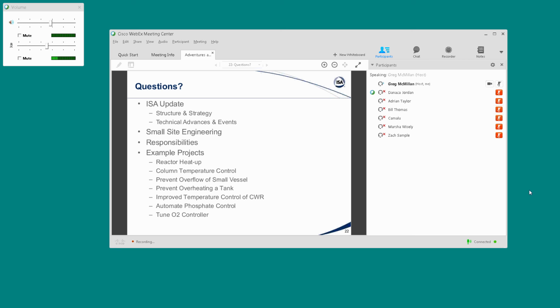Another common problem is that some older systems use the series form of the PID, whereas the newer DCS systems, the default is the ISA standard. Well, in the older DCSs, when you used the series form, you could set the rate time equal to or greater than the reset time, and you wouldn't get into trouble because the series PID had some interaction factors going on that effectively prevented rate action from dominating. You don't have that when you go to the ISA standard form.